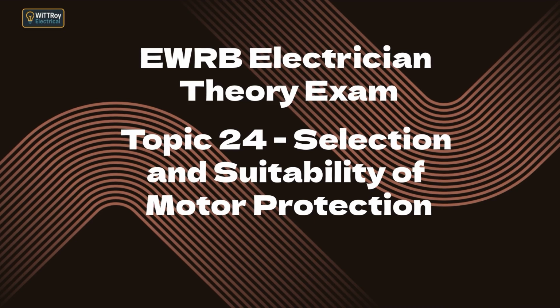Topic 24b. Describe the construction and operating principle of both thermal and magnetic overload units. 1. For three-phase motors. 2. For single-phase motors. Thermal overloads, three-phase and one-phase. Built using bimetal strips that bend when heated by motor current. Motor current flows through heaters inside the overload. If current stays too high for too long, the strip bends and opens a contact. This breaks the control circuit, dropping the contactor and stopping the motor.